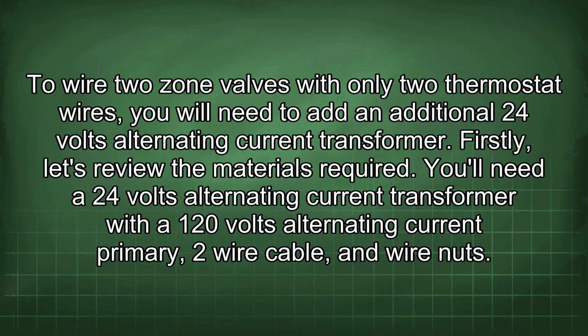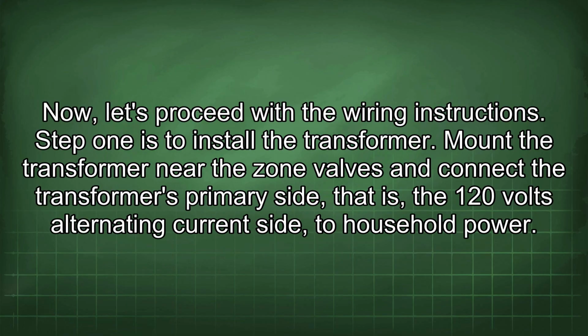To wire two zone valves with only two thermostat wires, you will need to add an additional 24 volts alternating current transformer. Firstly, let's review the materials required. You'll need a 24 volts alternating current transformer with a 120 volts alternating current primary, 2-wire cable, and wire nuts. Now let's proceed with the wiring instructions.